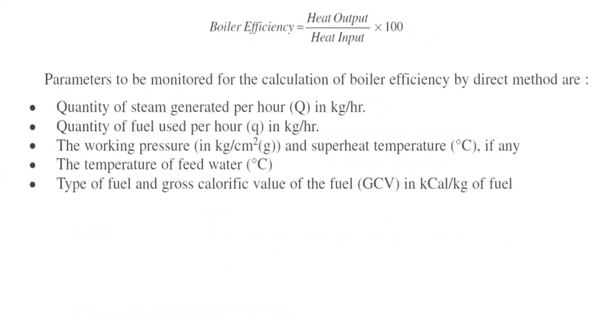Boiler efficiency is simply given as heat output divided by heat input, multiplied by 100. The parameters to be monitored for calculation of boiler efficiency by the direct method are: quantity of steam generated per hour in kg/hr, quantity of fuel used per hour in kg/hr, working pressure in kgf/cm² gauge, superheat temperature if any, and temperature of feed water, type of fuel, and gross calorific value of the fuel.